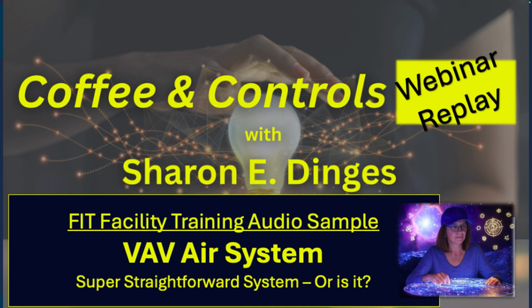And what we're doing is this air handler controls to supply temperature in the VAV air system. So supply as in, what is the temperature of the air that I'm sending down that ductwork that then can be distributed in my facility? So in this case, we are going through the VAV box. They need a lot of cooling. And so their damper, their air valve, is 100% open in this case.